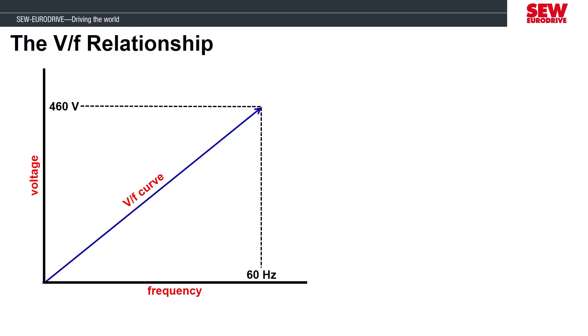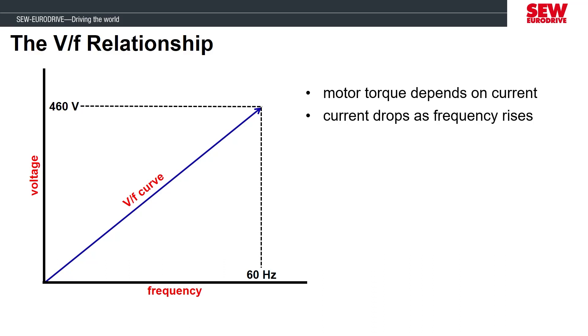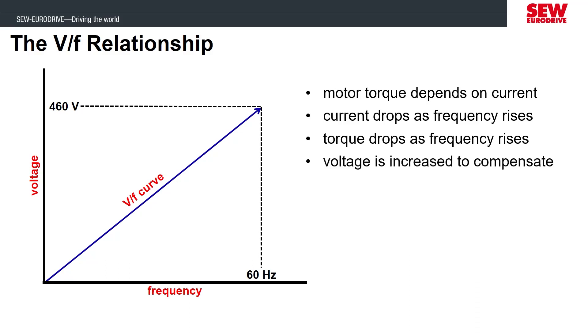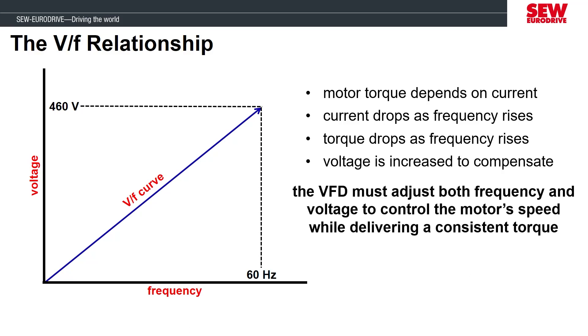Motor torque is dependent on how many amps are flowing through the windings, but there is a problem: as we increase the frequency to make the shaft turn faster, the motor windings start to oppose current flow. The higher the frequency commanded, the lower the current wants to be. If the current goes down, output torque also goes down. This isn't useful because we want the motor to deliver maximum rated torque at its maximum rated speed. So we compensate for the dropping current by steadily increasing the voltage in the motor as frequency increases. If we steadily increase the voltage, we can maintain a somewhat constant current, keeping the motor delivering constant torque through the speed range.